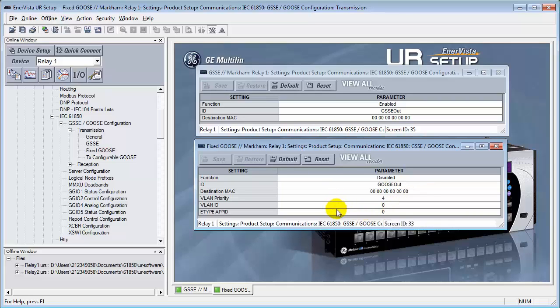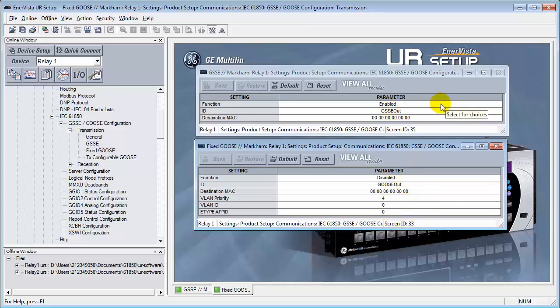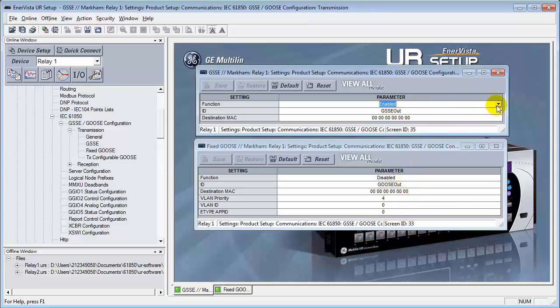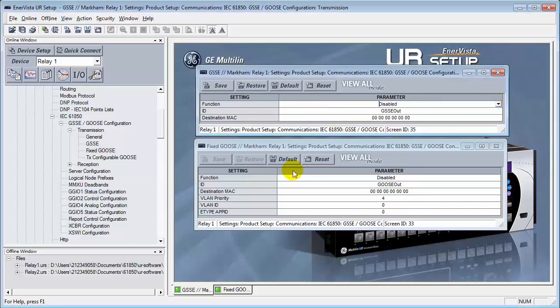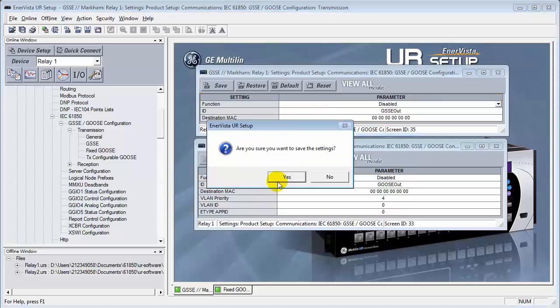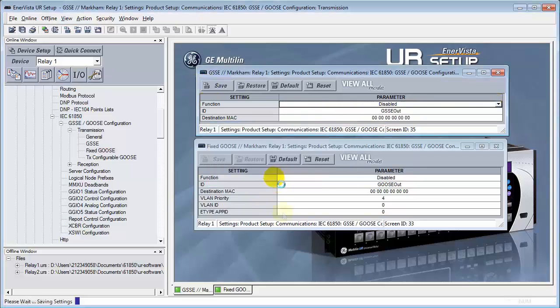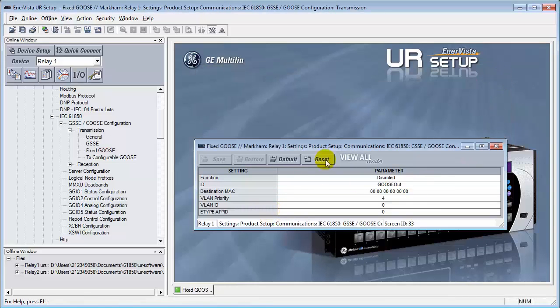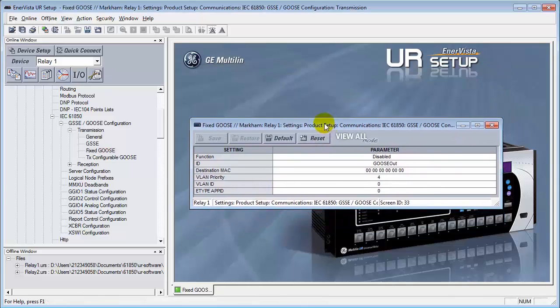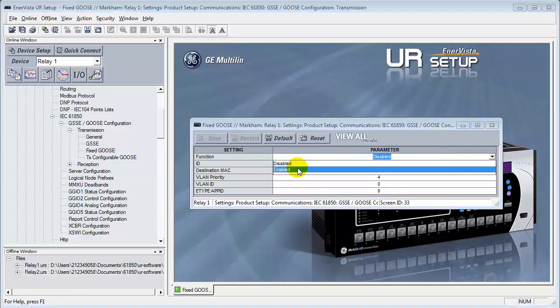This is why we're going to use the fixed goose as opposed to the GSSE. So first things first. Let's disable this. We'll save it. We'll close this down. No longer needed. Now with the fixed goose, we will now turn this on.